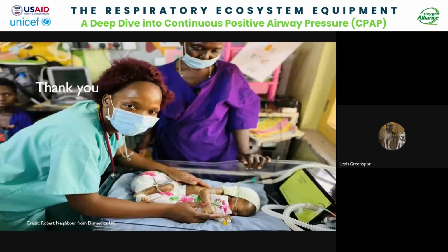And as you asked about ideal flow, you're looking at your PEEP, not your flow, if you're looking at bubble CPAP. That's what I alluded to, and Sarah went into a deep dive on the depth of the expiratory limb. You want your PEEP to be somewhere between 5 and 8 for newborns, depending on their work of breathing, and that's something you change according to how the patient changes. There are excellent resources online. Nest 360 actually has a lot of information about clinicians' guides for these types of things.